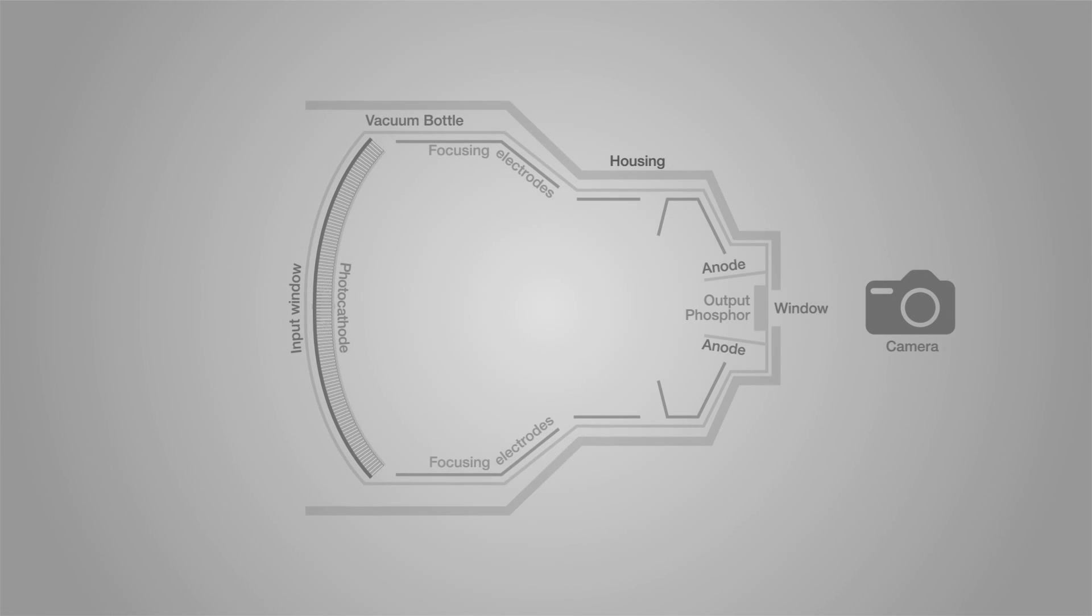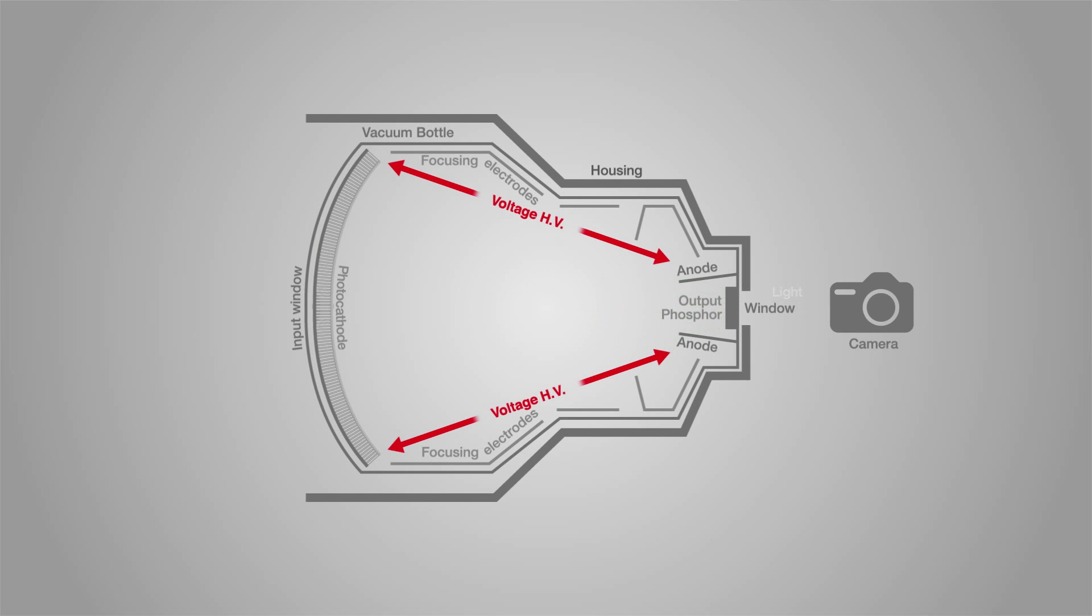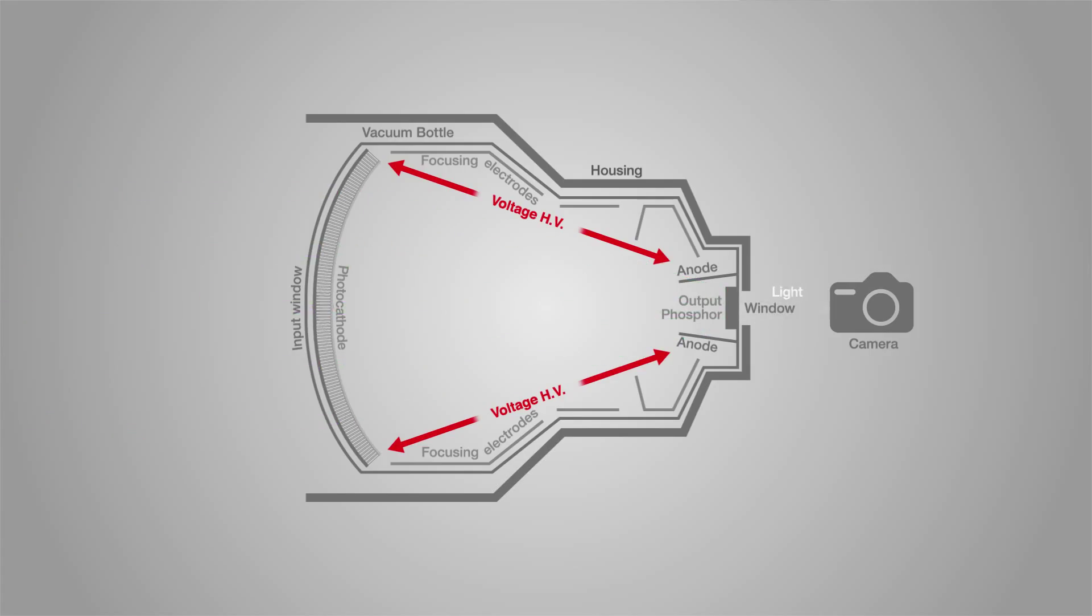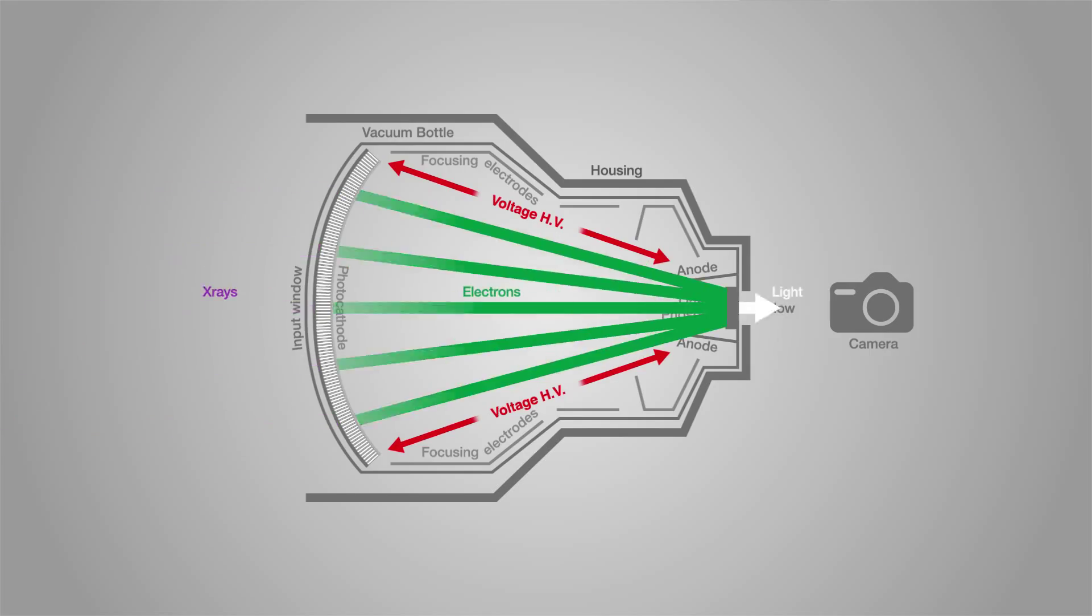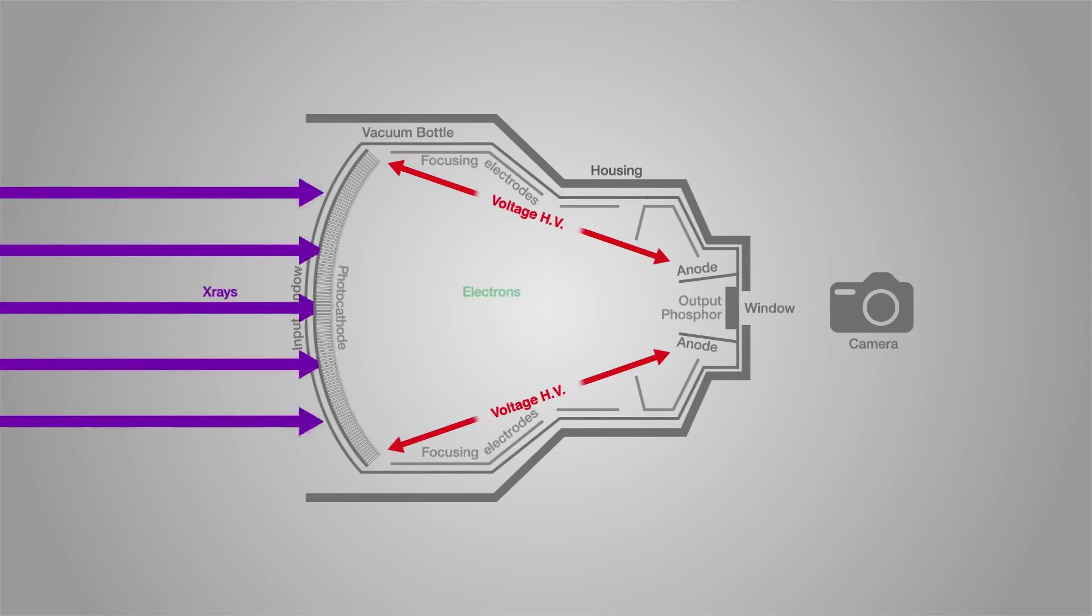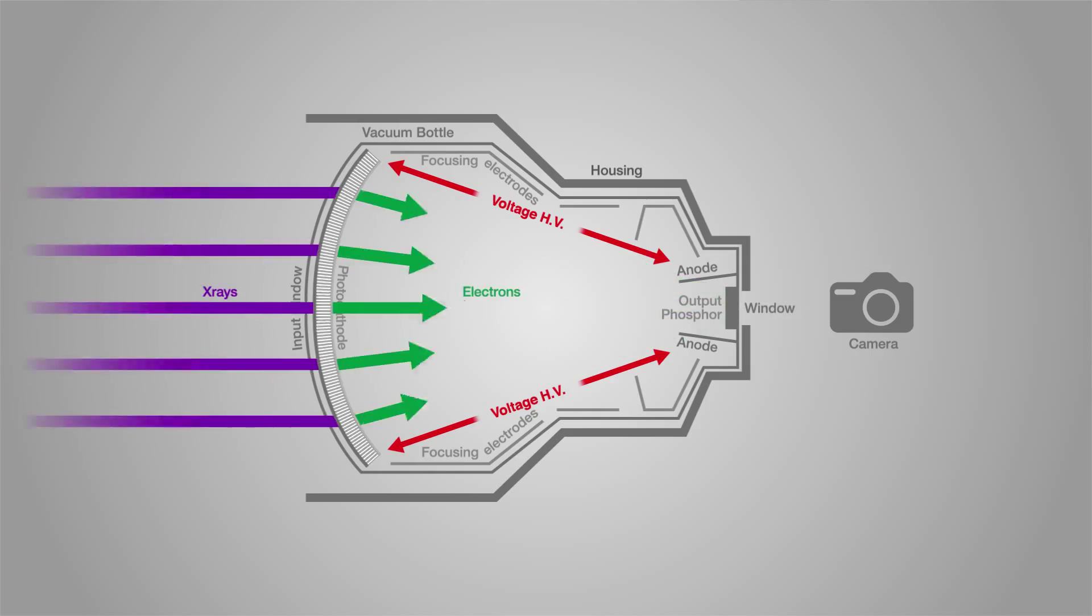The benefit of the image intensifier is that the signal intensity of the X-ray beam can be amplified through the selection of scintillator, the magnitude of the high voltage and the nature of the focusing components, which control the electron stream.